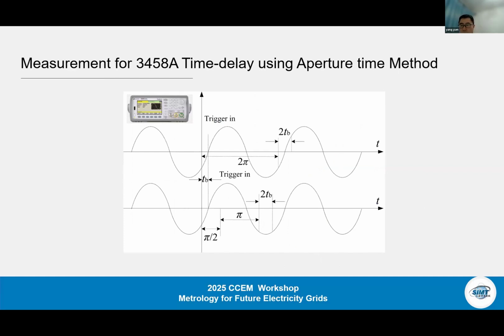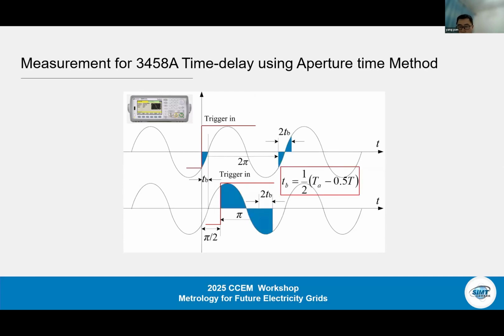So another method can be used to calculate the time delay introduced by the bandwidth by changing the aperture time of the DMM, taking advantage of the fact that the integral of a sinusoid wave has a zero mean value over an integral number of cycles. So the aperture time method has been proven to be effective at high frequencies. However, when the frequency decreases, the resolution of the integral value in the zero crossing region of the sine wave used to find the minimum becomes extremely small, due to the very small proportion of the time delay relative to the entire period. The latency caused by the bandwidth limit is hard to determine at frequencies below 10 kilohertz.